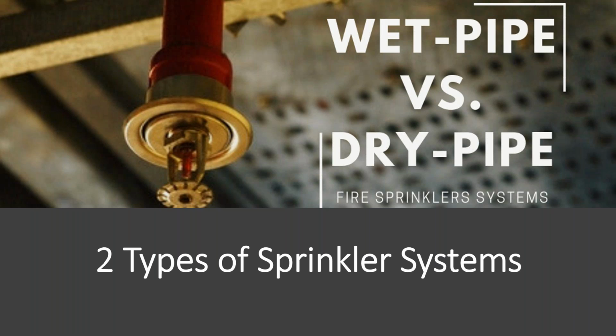Each one of these has its own advantages and disadvantages. You will typically see a wet sprinkler system in your office space, in warehouses, in apartment units, and the dry systems are normally installed in exposed locations, such as parking garages, outdoor patios, and balconies. So basically, if it is exposed to the cold elements here in the northern areas where we experience cold climate in the wintertime, then that's where you'll see a dry sprinkler system.